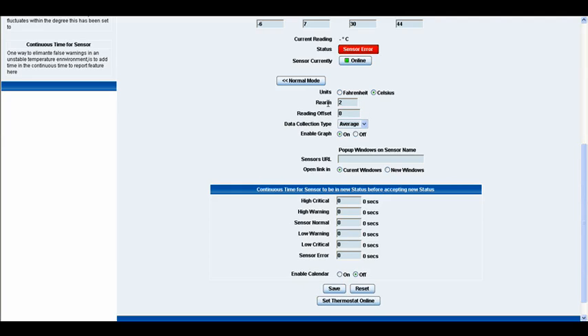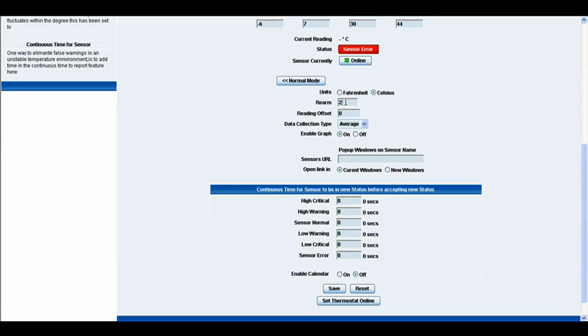Below that we have our rearm value. Now what the rearm does is essentially when a sensor comes out of a high critical or a low critical or any other one and it reverts back to a normal status. In here you input the time in seconds that it has to be in that status before it will accept it and display the normal reading. So, for example, if it comes out of the high critical and it goes into normal at present, once it's been in that normal status for two seconds it will then give you a normal reading.